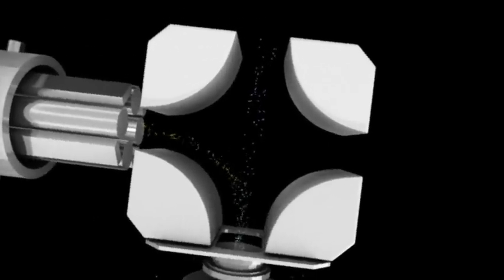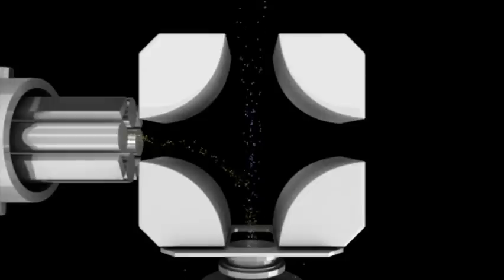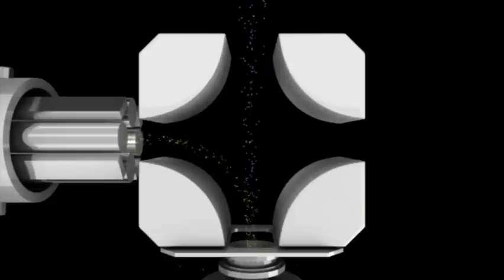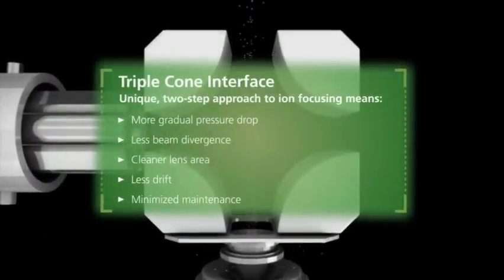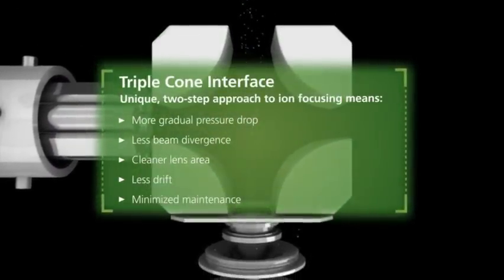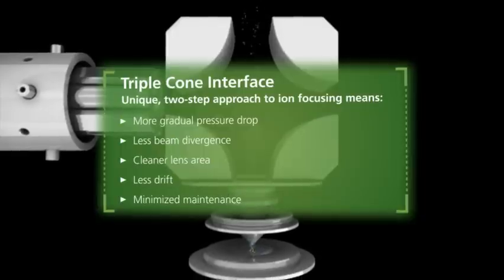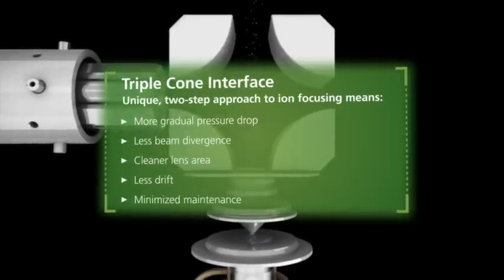The three cones also shape the beam before it enters the quadrupole ion deflector, a breakthrough filtering feature that turns ions 90 degrees, focusing those of a specified mass and discarding all neutral species. The unique combination of the hyper-skimmer and the quadrupole ion deflector offers exceptional signal stability. Even when running the most challenging matrices, Nexion allows you to keep the same signal response hour after hour.